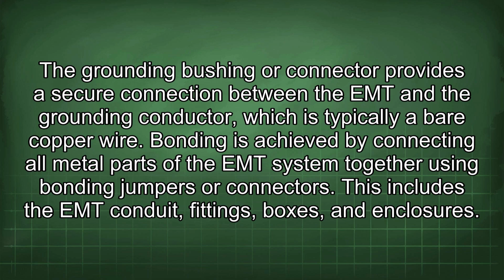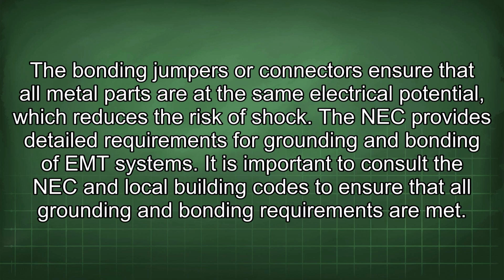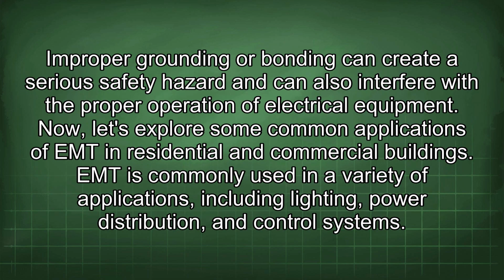Bonding is achieved by connecting all metal parts of the EMT system together using bonding jumpers or connectors. This includes the EMT conduit, fittings, boxes, and enclosures. The bonding jumpers or connectors ensure that all metal parts are at the same electrical potential, which reduces the risk of shock. The NEC provides detailed requirements for grounding and bonding of EMT systems. It is important to consult the NEC and local building codes to ensure that all grounding and bonding requirements are met. Improper grounding or bonding can create a serious safety hazard and can also interfere with the proper operation of electrical equipment.